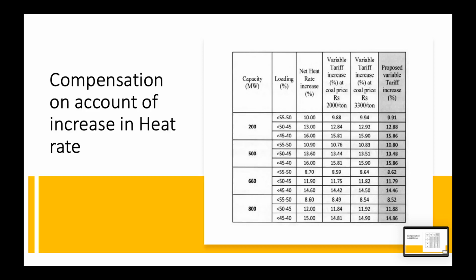But in the new guidelines it has been decided that if the thermal power plant shows the loading between 50 to 55%, a net heat rate increase of 10% would be considered for 200 megawatt, and for 500 megawatt it would be 10.9 percent, and for 660 and 800 megawatt it would be 8.7 percent and 8.6 percent respectively. The maximum compensation on the net heat rate would be 16% for showing the loading between 45 to 40% for both subcritical units of 200 megawatt and 500 megawatt. For supercritical units, that is 660 and 800 megawatt, the maximum compensation on showing the loading between 40 to 45% would be 14.6 percent and 15% respectively.